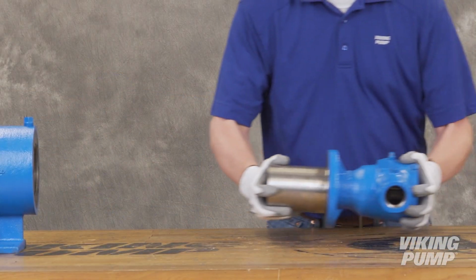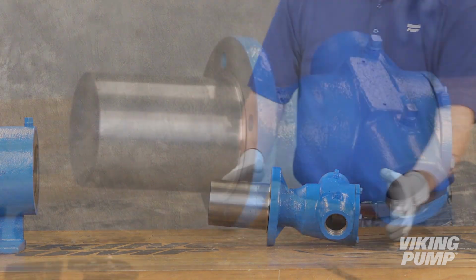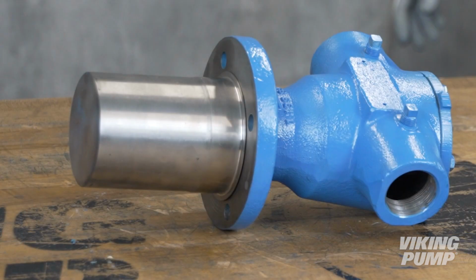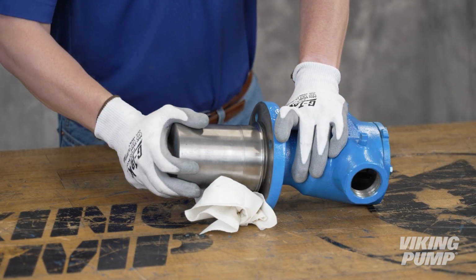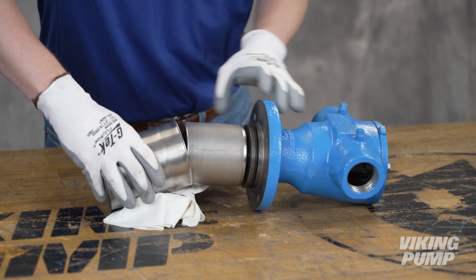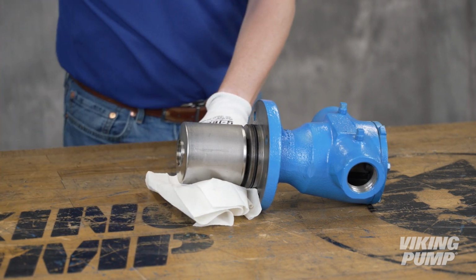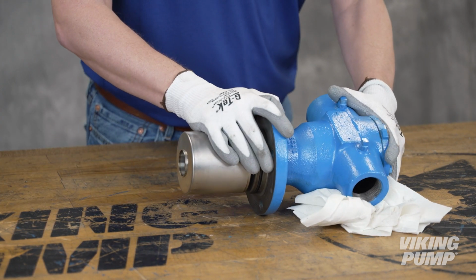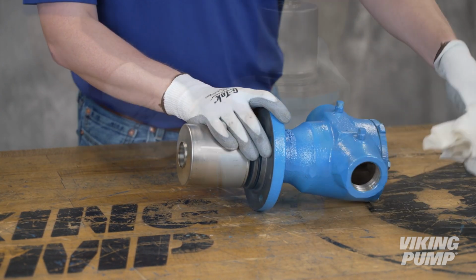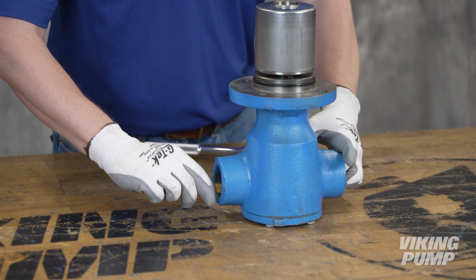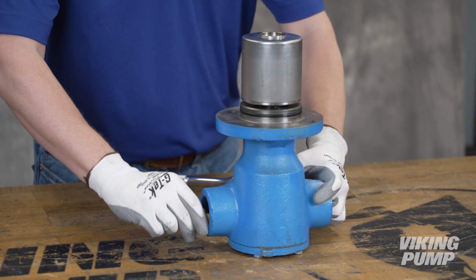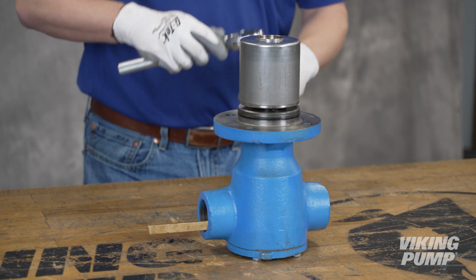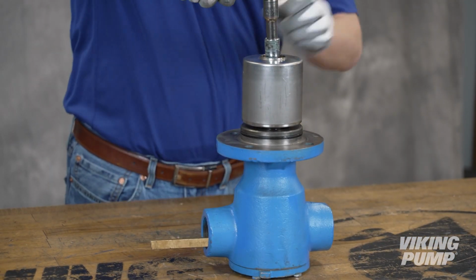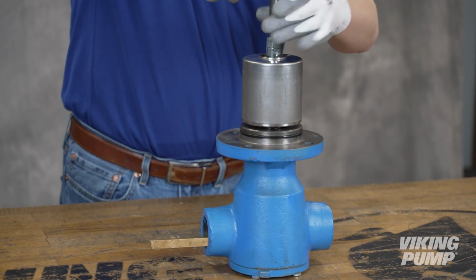When setting the pump or inner magnet down, be careful not to set it near any iron or steel objects which may be attracted or damaged by the magnet. Remove the canister. Ensure to pull it straight off and use caution, as it will likely be full of liquid. Drain the pump of any residual liquid by turning the shaft. For B and C size magnets, insert a brass bar through a port between the gear teeth to prevent the shaft from turning. Loosen and remove the cap screw and lock washer.